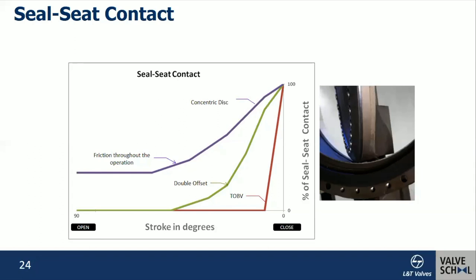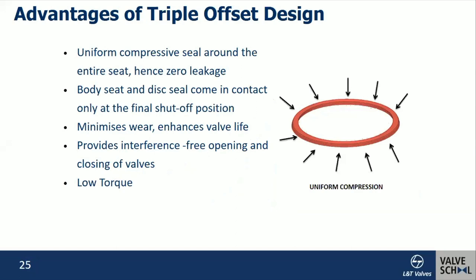To recap: in a concentric valve, constant disk friction occurs throughout the operation. In the double offset, rubbing takes place after approximately 50% of the operation. In the triple offset butterfly valve, after reaching the seating face, torque is applied to create metal-to-metal sealing — making the laminated seal expand on the seat faces. The laminated seal provides uniform compression around the entire seat, hence zero leakage is observed. The body seat and disk seal come in contact only at the final shutoff position, which minimizes wear and enhances valve life. Because of the interference-free opening and closing, torque is also lower.